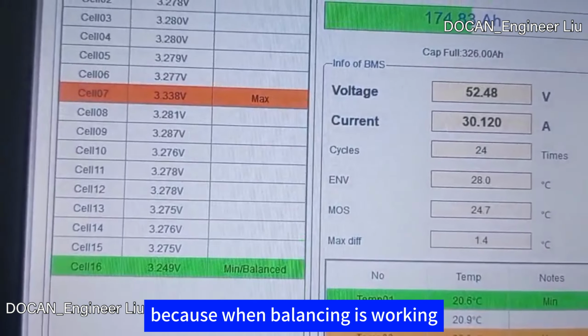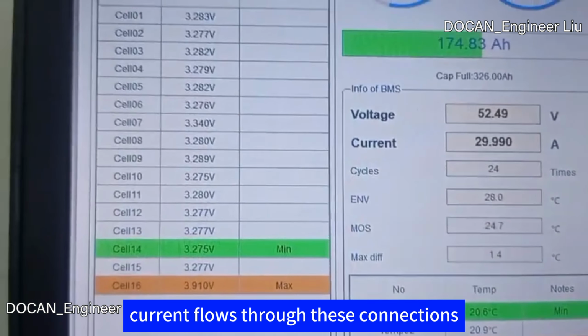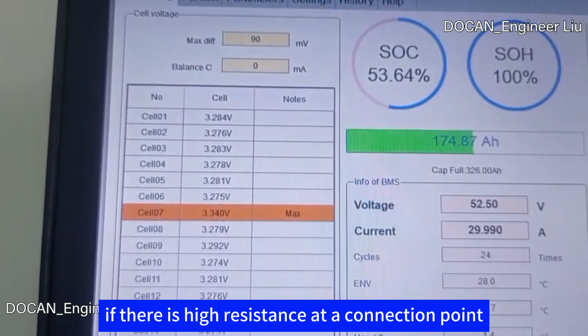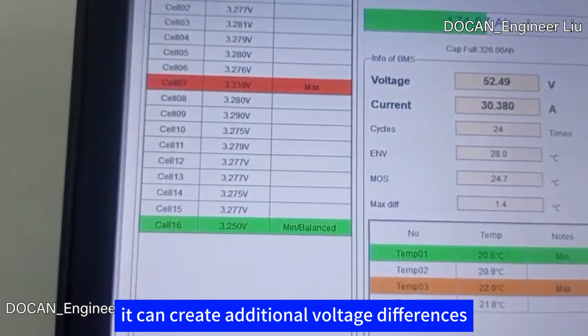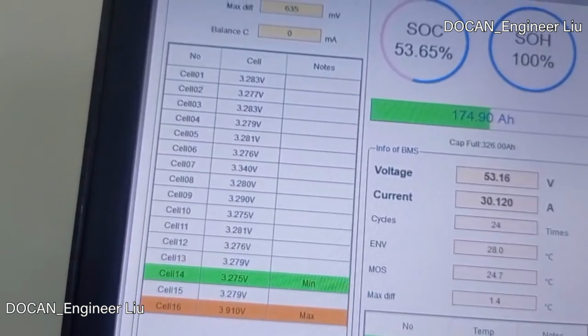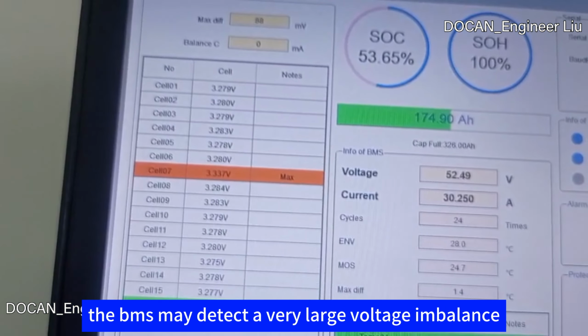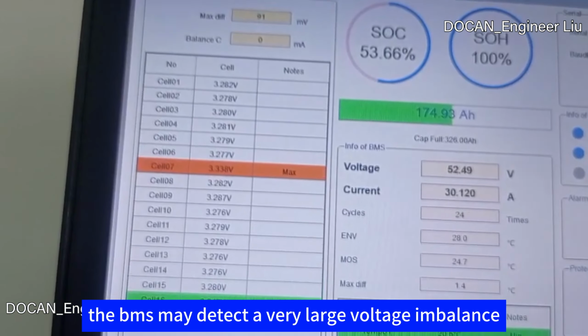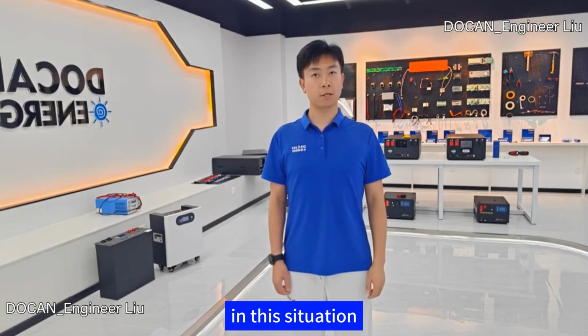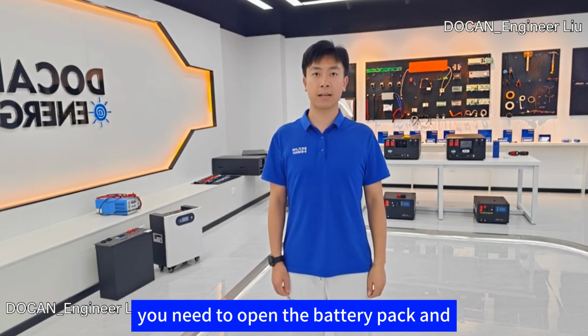Because when balancing is working, current flows through these connections. If there is high resistance at a connection point, it can create additional voltage differences. As a result, the BMS may detect a very large voltage imbalance. In this situation, you need to open the battery pack and carefully check all connection points.